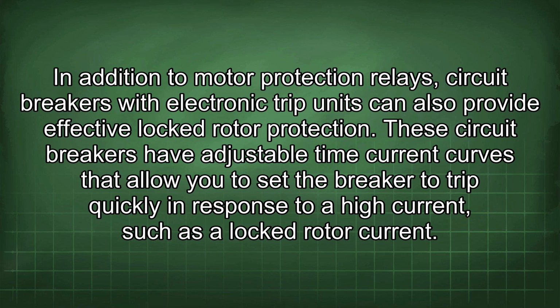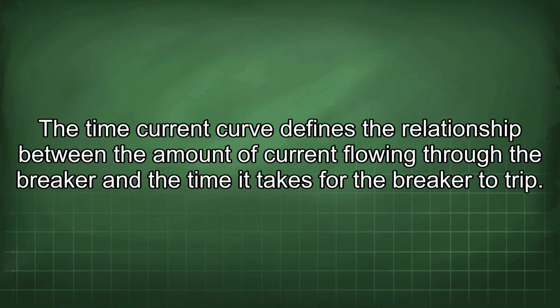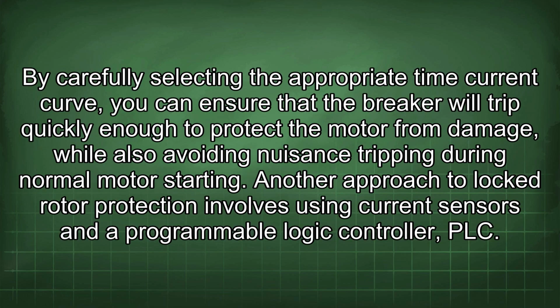In addition to motor protection relays, circuit breakers with electronic trip units can also provide effective locked rotor protection. These circuit breakers have adjustable time current curves that allow you to set the breaker to trip quickly in response to a high current, such as a locked rotor current. The time current curve defines the relationship between the amount of current flowing through the breaker and the time it takes for the breaker to trip. By carefully selecting the appropriate time current curve, you can ensure that the breaker will trip quickly enough to protect the motor from damage, while also avoiding nuisance tripping during normal motor starting.